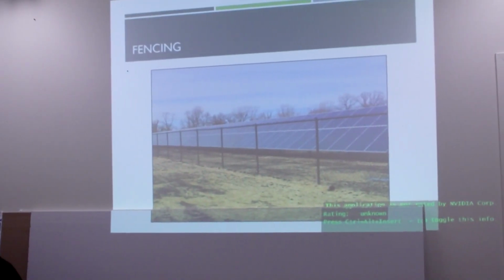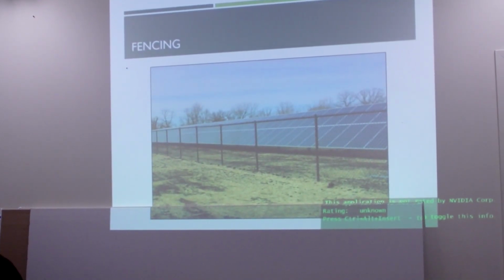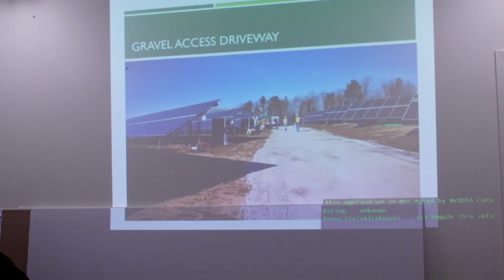The site will be fenced all the way around its perimeter. This is a 1500 volt system, and NEC now requires that 1500 volt systems or greater be perimeter fenced. Also, all of our equipment on the project will be locked, so if there are trespassers, there's still a level of safety from anybody getting hurt attempting to do what trespassers do.